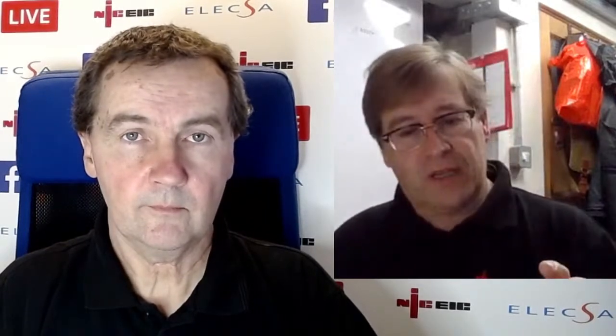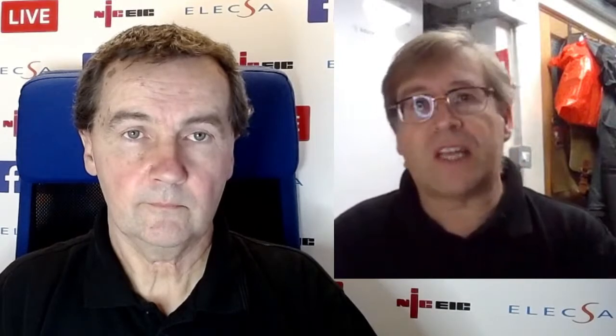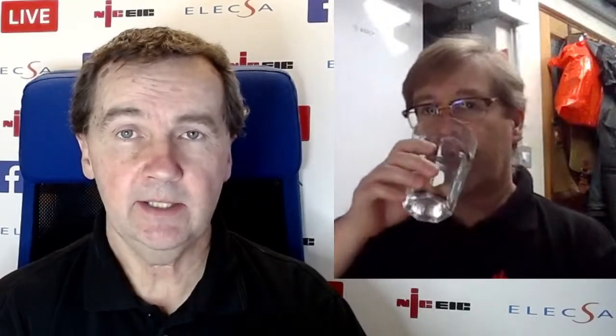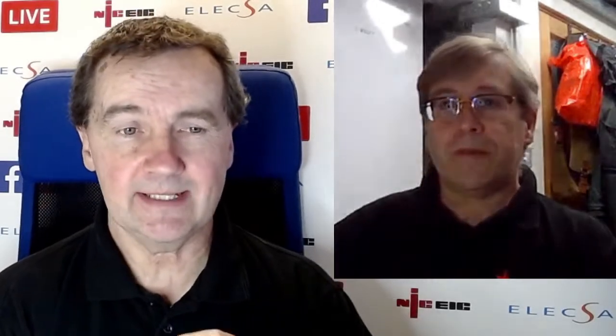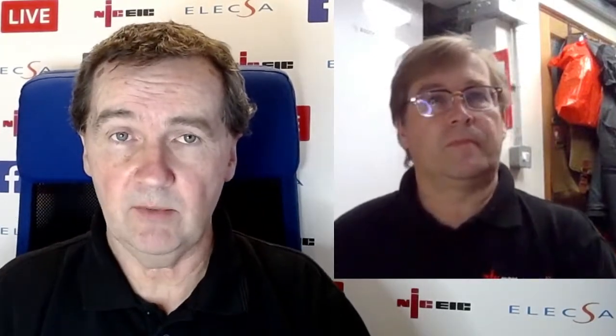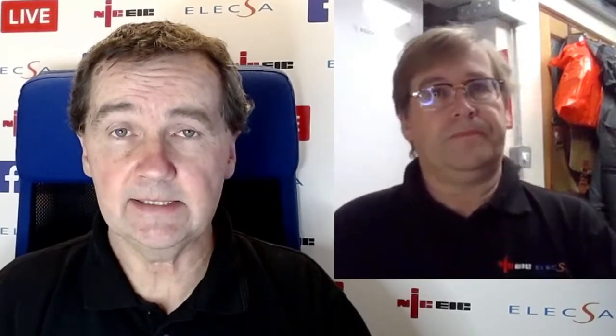We have to bear in mind that the higher up the current rating you go, it has the opposite effect on Zs. You start to restrict yourself with circuit Zs, don't you? So that could be a limiting factor when choosing your device. Yeah, it's quite a key point, isn't it? Although a Type C for the same rating as a Type B will give you a higher current before it operates, in order to achieve that higher current, you've actually got a tighter Zs to achieve. So sometimes, because of, for example, the length of your circuit, you might not be able to use a Type C, and then you would have to go to a Type B, which has got a larger Zs to achieve. So yeah, it is a consideration. But as you rightly said, the key thing is that it's all about the instantaneous current for instantaneous operation.